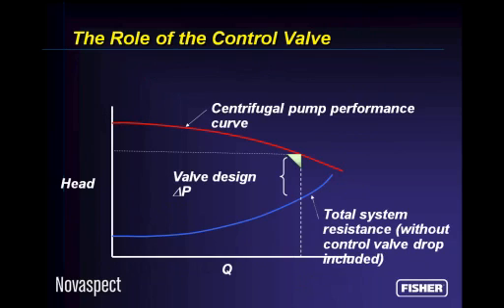a new valve. The role of the control valve in the process is to create resistance and use up additional pressure drop. The blue line is the total resistance, the hydraulic balance, if you will, of a process without including the control valve, and that red curve is a centrifugal pump performance curve. The difference between this point and this point is the number that your engineer used when the plant was designed as far as how much pressure drop did we tell the valve vendor at that particular point that we were going to allow him to consider across the valve to get the flow rate through the valve.